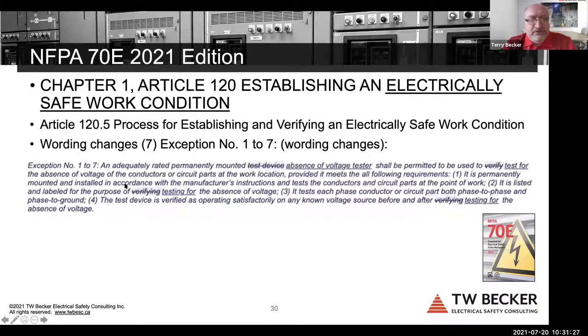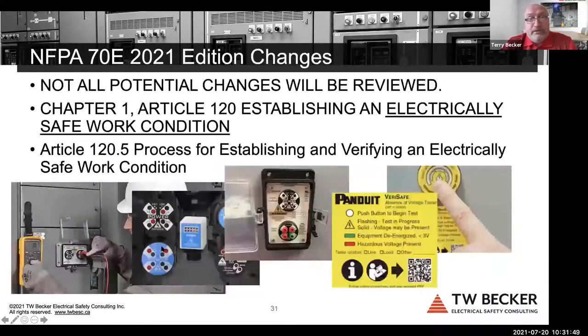And then specifically, this is from the public review comment, to further clarify again this automatic voltage tester in the language. So absence of voltage tester, not a test device. Again, testing for absence of voltage, not verifying. So the automatic voltage testers, specifically the product from Panduit that came to the market early, and there's another product from iGuard in Canada versus the products from Grace Technologies. So one is automatic, one is manual and requires the qualified electrical worker to do a test, as you can see in the picture.